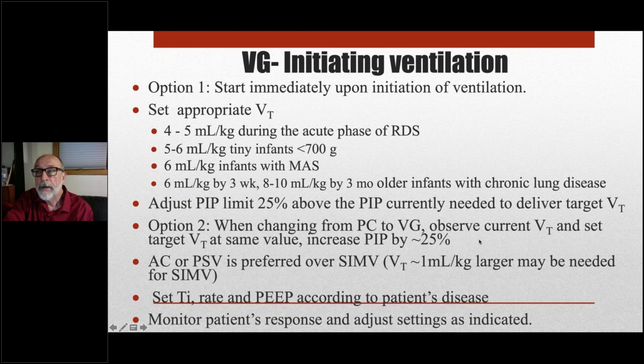And it is important to keep in mind that the relationship between lung compliance, inflation pressure, and delivered tidal volume is the same whether you're adjusting the inflation pressure manually, as in pressure control, or if you're using volume guarantee and the ventilator is adjusting it automatically. Same pressure given the same compliance will give you the same tidal volume. The difference is you're prioritizing tidal volume as your primary control variable that you want to keep stable over pressure. And we should get over our barophobia and recognize that volume is the most important factor that leads to lung injury. Okay.